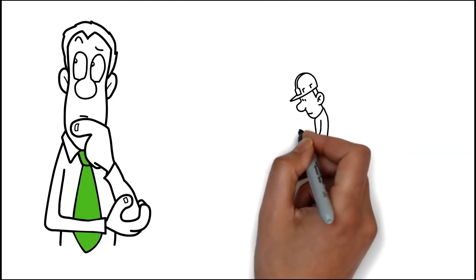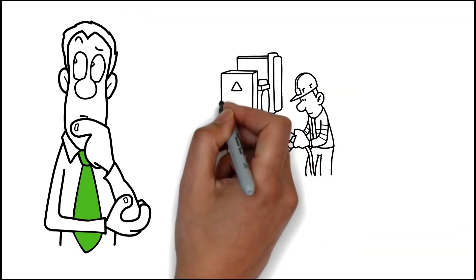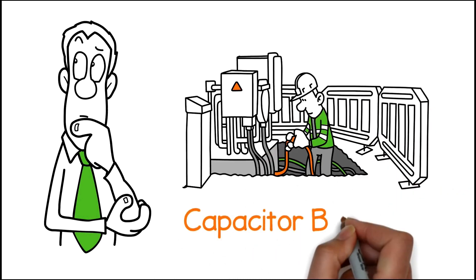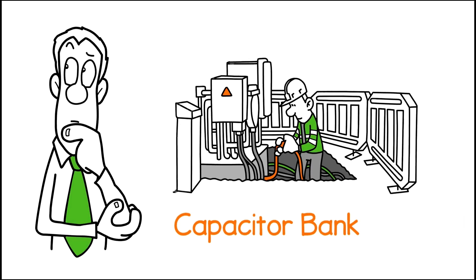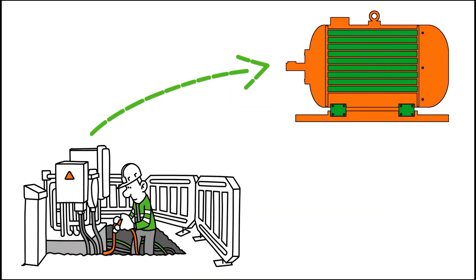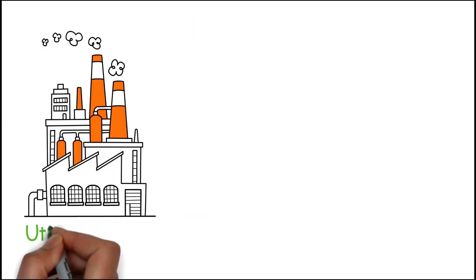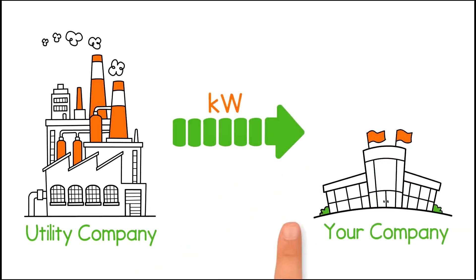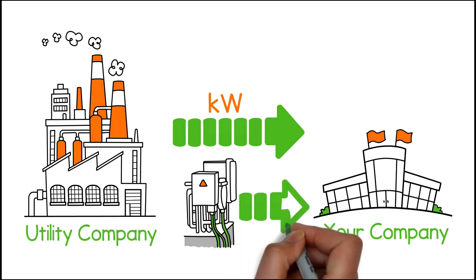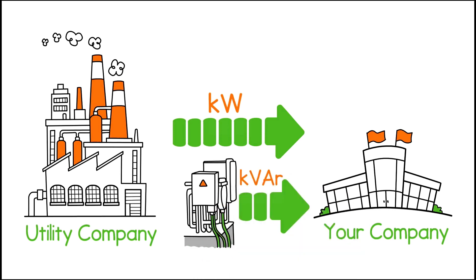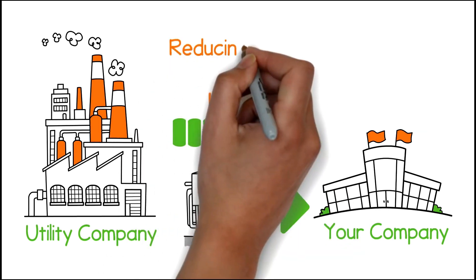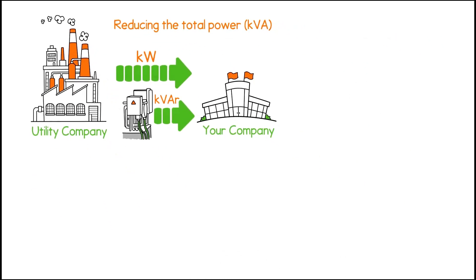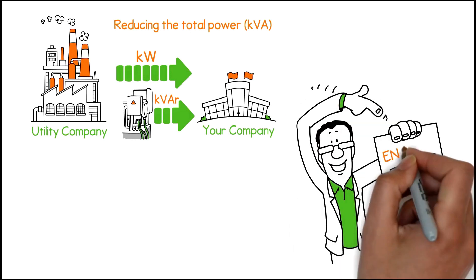How do you get rid of this charge? By installing a custom-designed power factor correction system, also known as a capacitor bank. These temporary storage units provide reactive power to your motors instead of receiving it from the utility company. Both kilowatts and KVAR come from the utility. When a capacitor bank is installed in your facility, it replaces the reactive power supplied by the utility, thus reducing the total power — KVA — delivered to your facility. Reduced power from the utilities equals reduced costs.